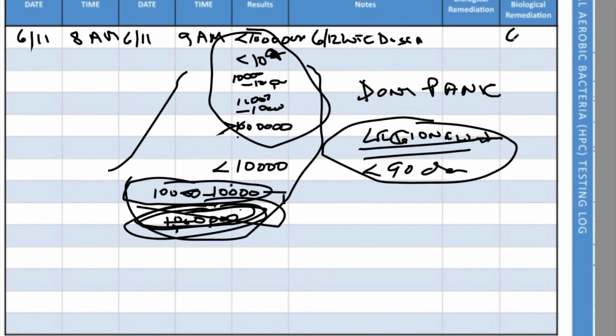I wrote it into the notes section there, along with the type of remediation - it might just be an extra dose. The Department of Health wants you, once you've had a high bacteria count over 10,000, 100,000, or a million, to retest the total bacteria 3 to 7 days later. Since you're testing weekly anyway, you're almost automatically satisfying that requirement. So next week you'd be doing this again, and the week after that you'd be doing this again - each week taking a sample and adding to this list of bacteriological sample results.